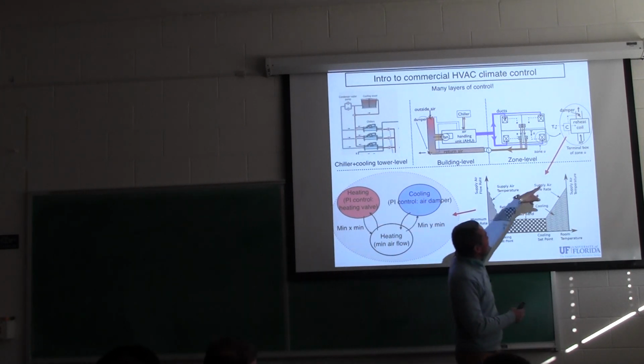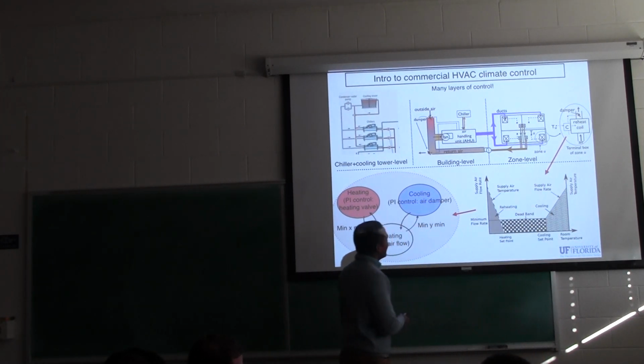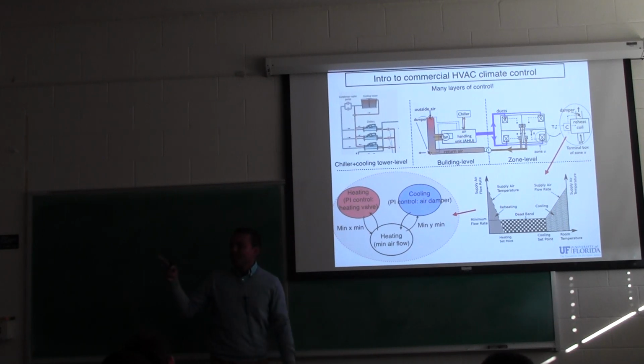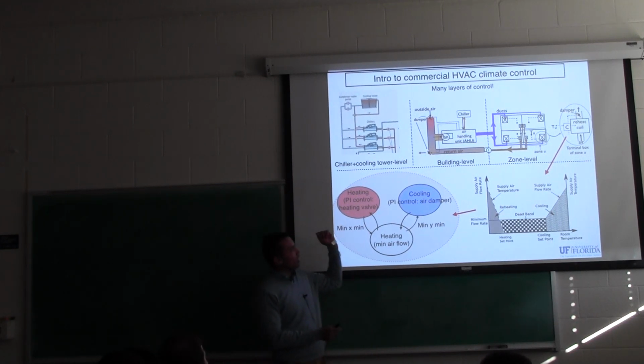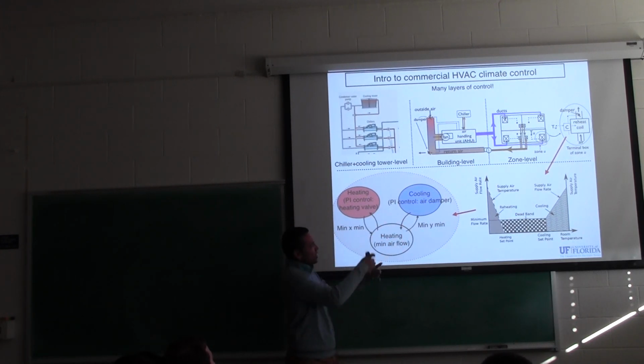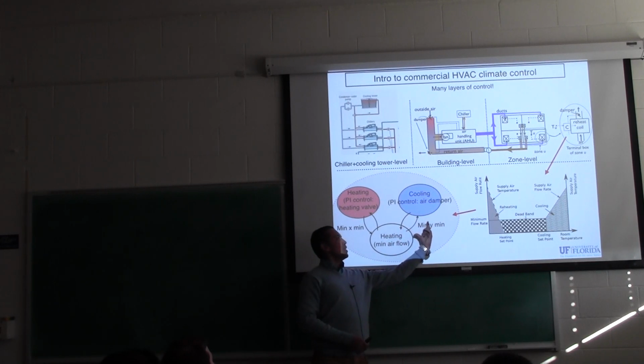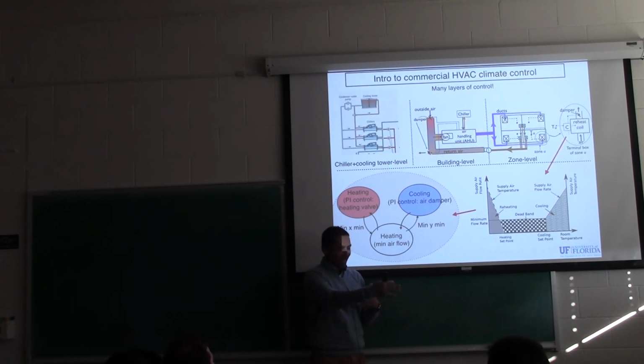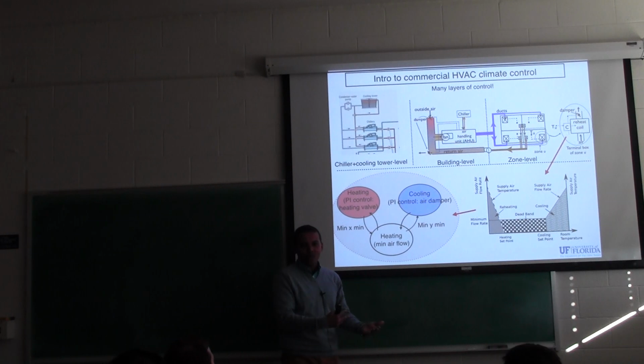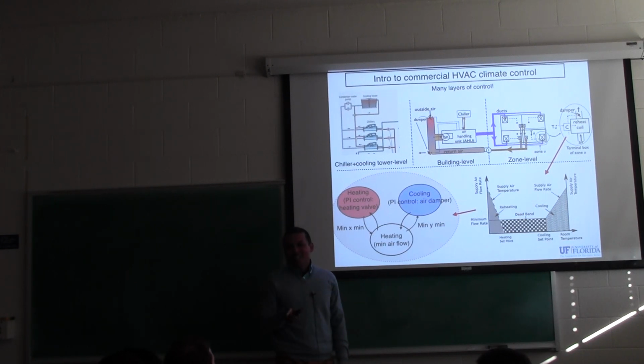So once you start affecting the climate control, you think changing the temperature set point is going to lead to a change in the fan power and so on. But depending on how the transitions are taking place, just because of these dwell time conditions, there could be a 10-minute delay between what you think will happen and what will actually happen. It also may not happen, but also may happen. I'm not saying that this will never work. The problem is that you would not know when it's not going to work because of all this complexity.